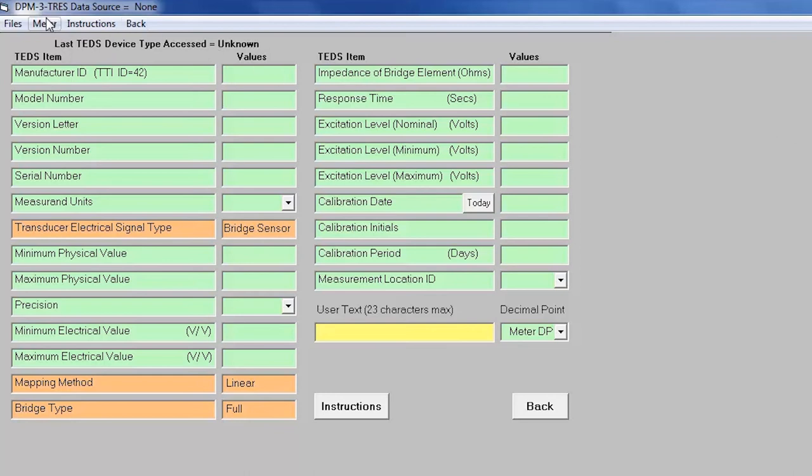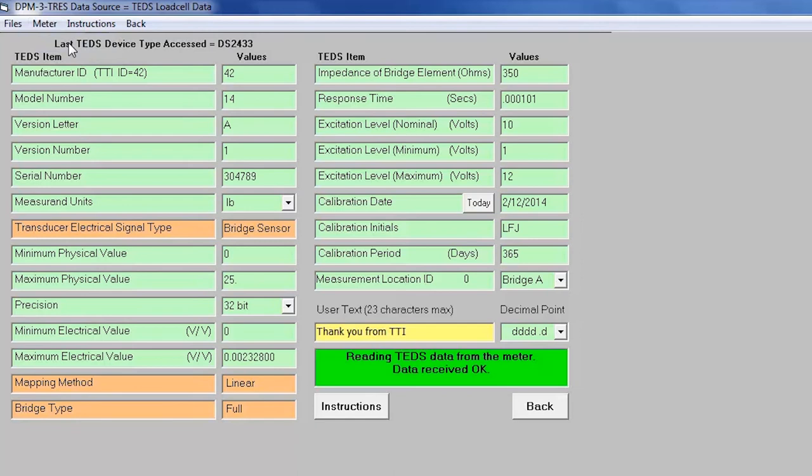From the control bar, click meter, then click read to populate the template. This allows you to edit any of the parameters in the template and write the new parameters to the EEPROM, or you can save to a file for future reference.